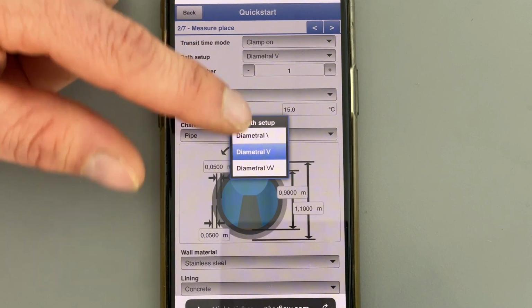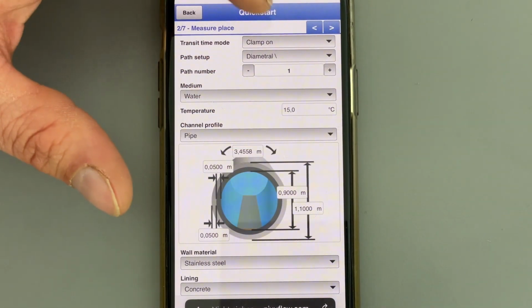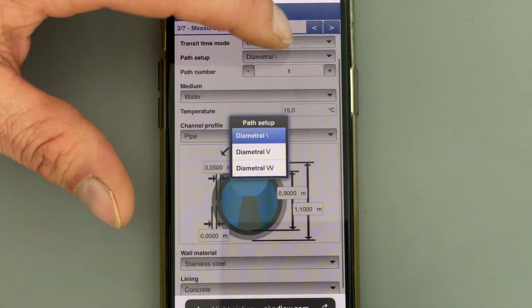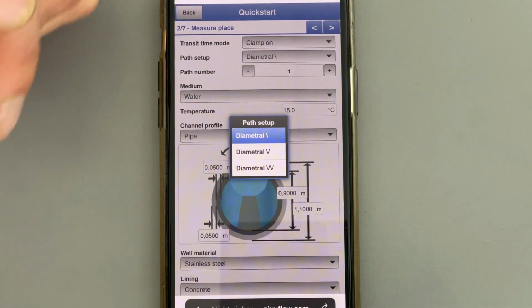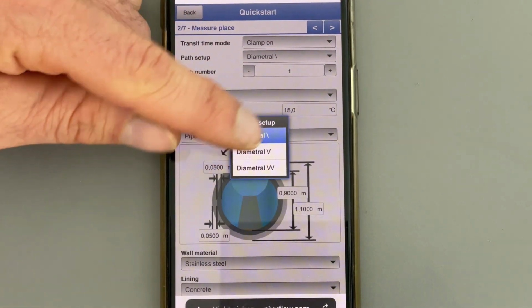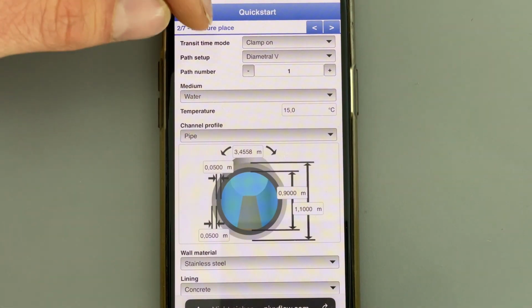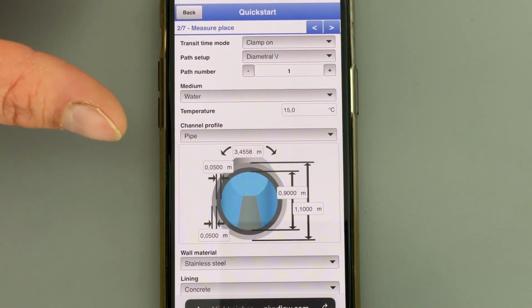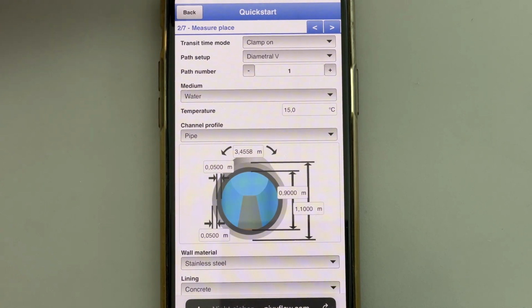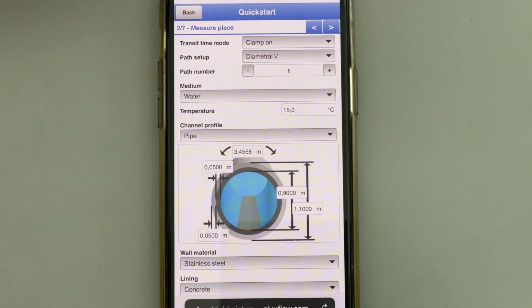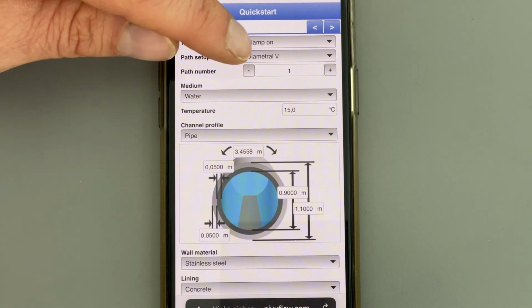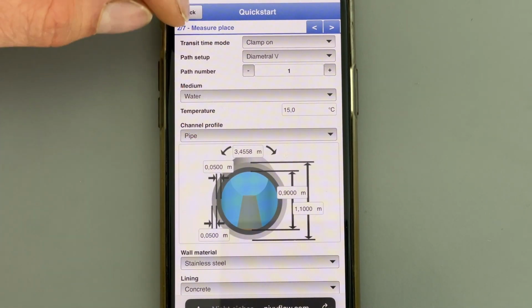If you use diametral, only one dash, it means the sensors need to be installed on opposite sides of the pipe. For V and W, the sensors need to be installed on the same side of the pipe, and on V you have 2 times the signal traveling through the medium, and in W 4 times.